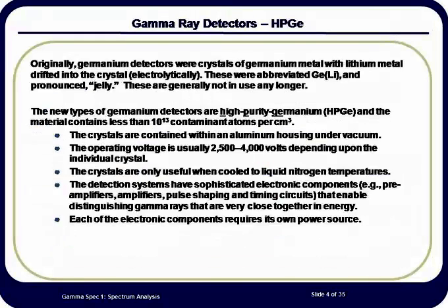Older Ge(Li) detectors could not be warmed to room temperature, as the lithium would drift out of the crystal, making the detector inoperable. Today, most labs use high-purity germanium, or HPGe crystals, where they can be warmed to room temperatures and then cooled back down again and operate as well as they did when first used. However, each electronic component of the high-purity germanium system has a separate power source required in order to get the high degree of resolution required for exacting gamma ray analysis.